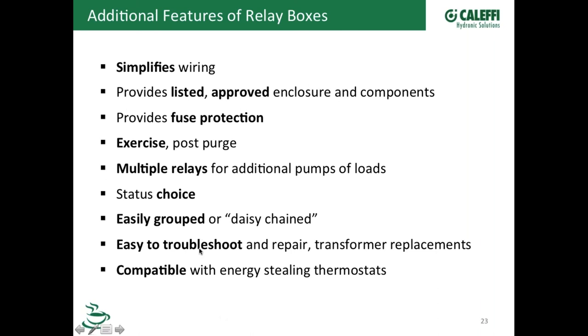Easy to troubleshoot. There's lights on there that are going to tell you when you've got a call for heat, when the zone valve or the actuator is powered up and stuff like that. And they are compatible with the different types of thermostats out there. Some of them are energy stealing and they need a common wire.